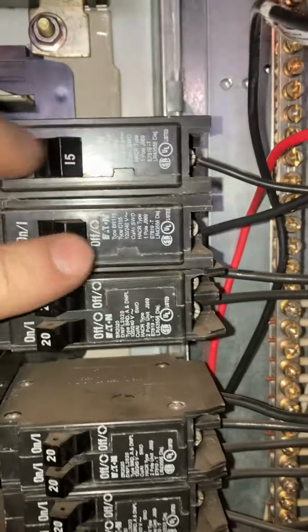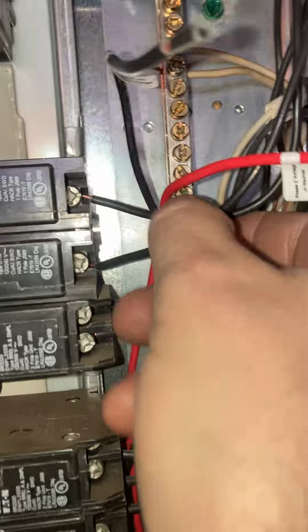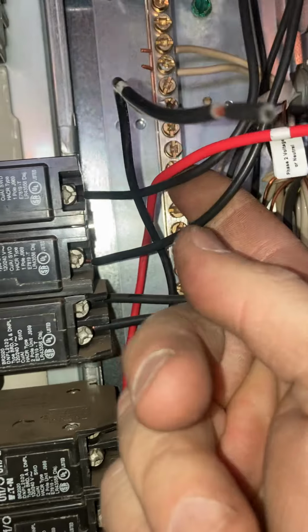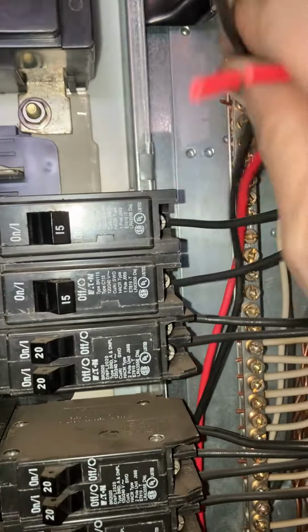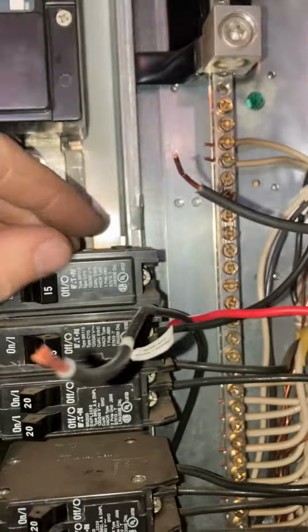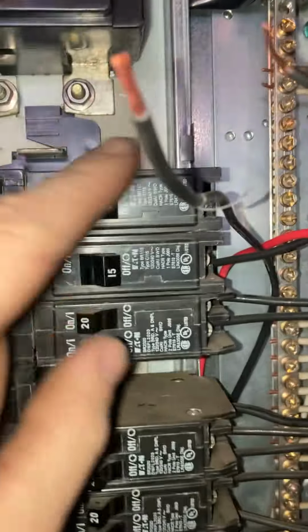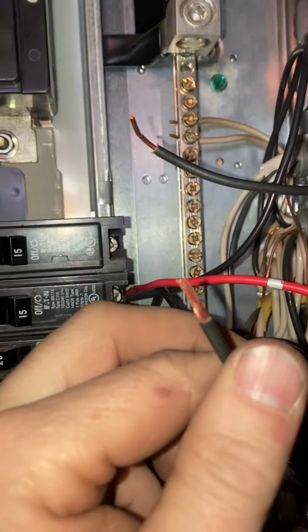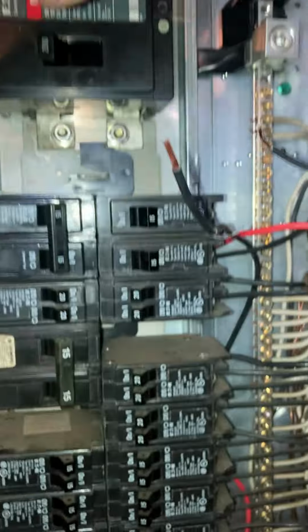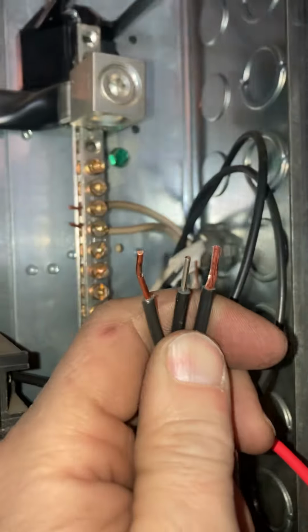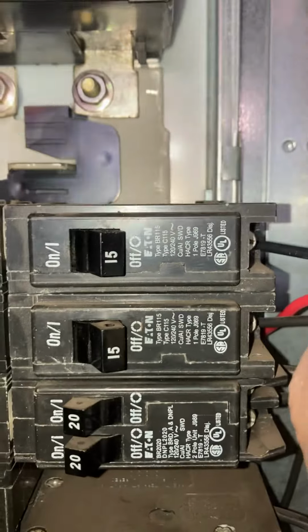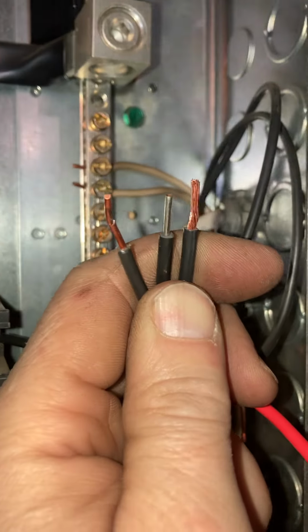So I'm going to take these 2 and shut them off, and pull these 2 wires out, remembering where each one goes, and daisy chain into that. I've unhooked the wire going into that circuit, and this is the one going to the Emporia. Now I've grabbed my jumper wire, and I'm going to jumper it into the back side of this. Now I have 3 wires: the jumper wire coming out of my circuit breaker, one going to the Emporia, and one going to my load.